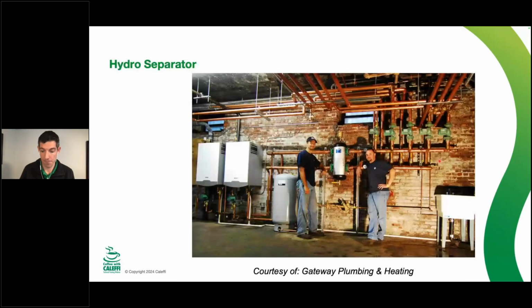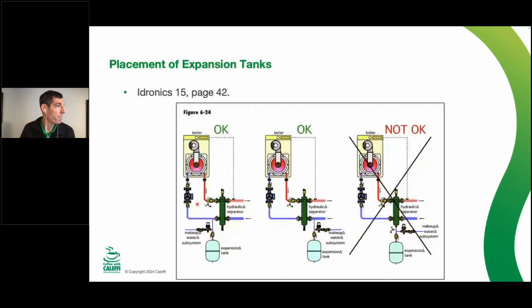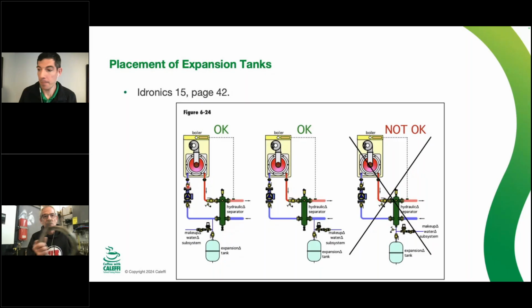One of the typed in questions asks why we pump into the boiler. So go back on that slide and I'll show you a little example here. That boiler in the picture right there is what's called a water tube boiler. And this is what it looks like right here. This is one of the sections that came out of that exact boiler. And if you can see the passageway in that, I don't know if you can see it in the camera very well, we hold it against the white, it's pretty small.